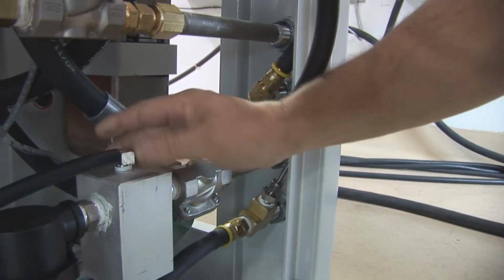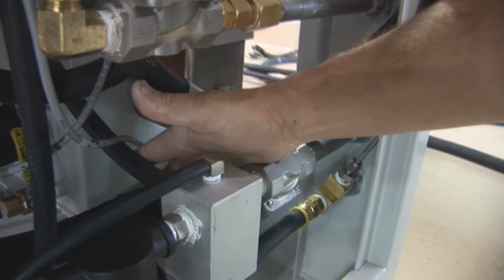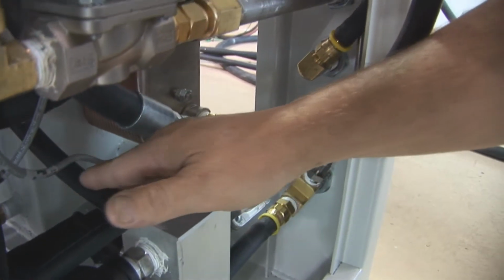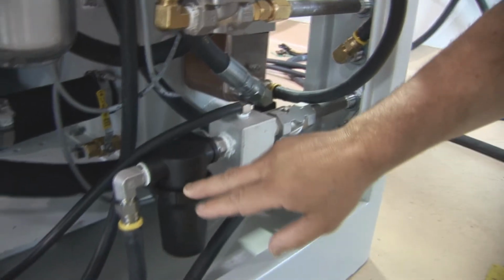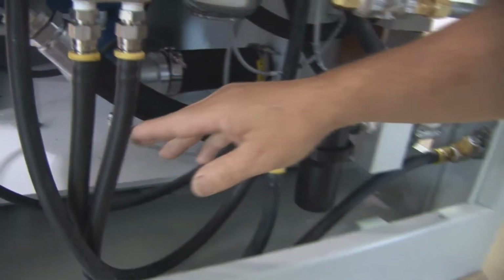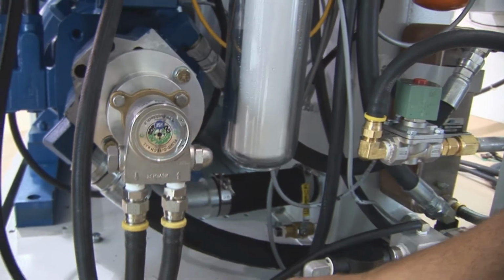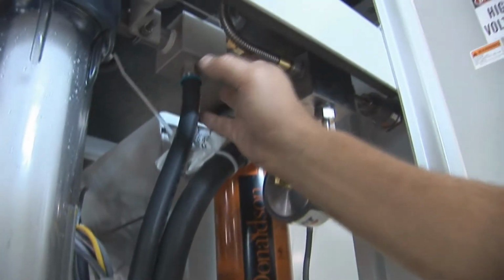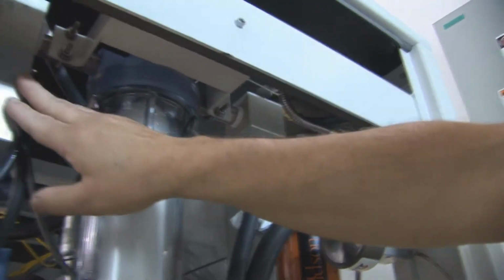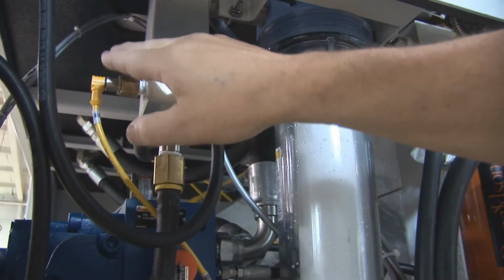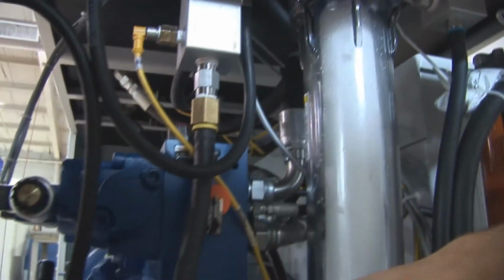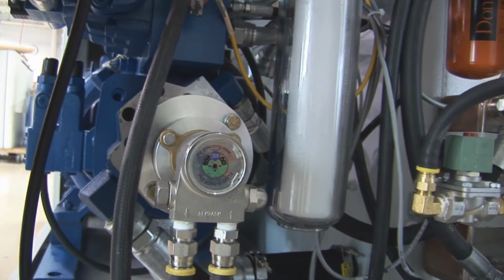Now we're going to discuss the low pressure water system, show you where the water comes in and how it goes through these components. We have the inlet water coming in through here, through a solenoid valve, through a manifold, which we have a 30 psi switch back here. It goes through there through a strainer. From the strainer it goes up to your booster pump. From your booster pump it goes up to your filter assembly. Through the filter assembly it goes to another manifold that has your 128 degree switch on it. If your booster pump overheats up to 128, you'll shut down.